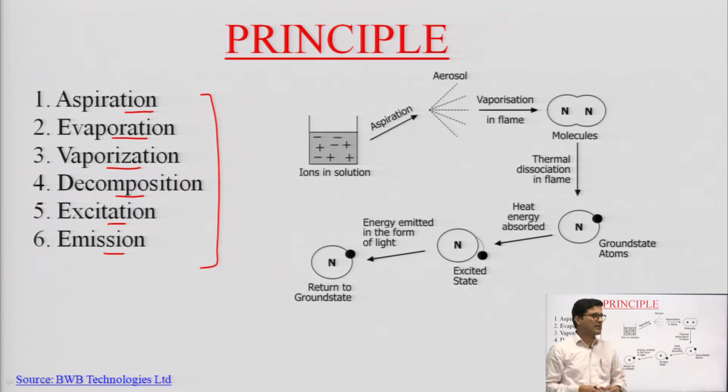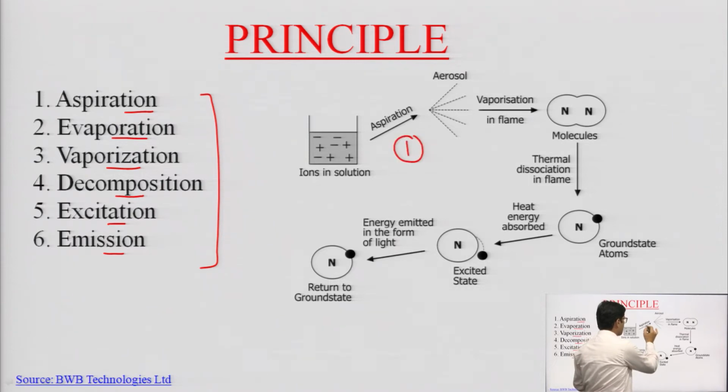The first is the aspiration step. Aspiration is the introduction of the sample into the flame in the form of a fine mist or fine droplets, which is mainly carried out by the atomizer or nebulizer component of the instrument in the form of an aerosol. So in aspiration we introduce the solution of the sample into the flame in the form of an aerosol.